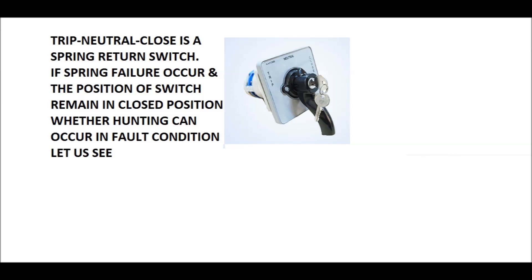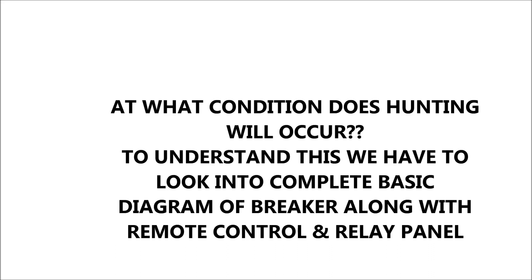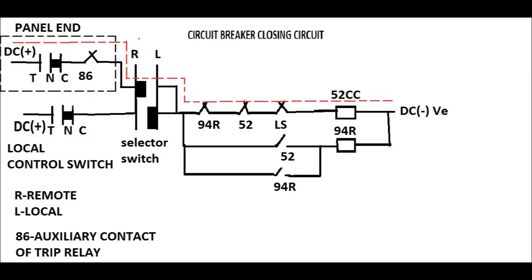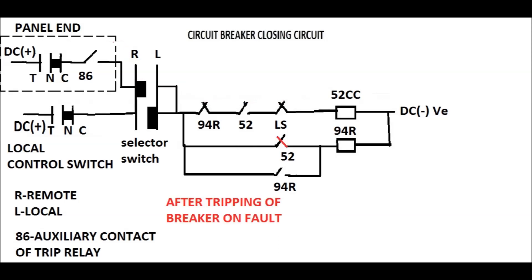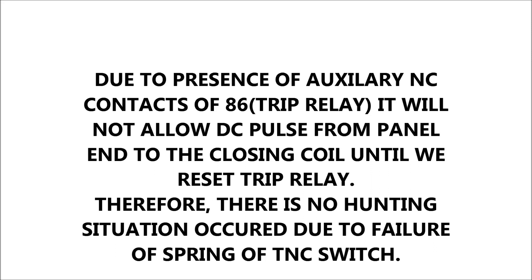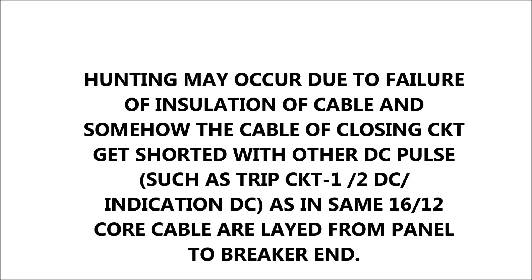At most sites, hunting may be thought to arise due to failure of the spring return of the TNC control switch. As shown in this figure, if we press the control switch to the closed position, it will automatically return to the normal position due to the spring. However, to understand whether spring failure can cause hunting in the absence of an anti-pumping relay, we must go through the complete circuit diagram from the panel end to the breaker end. In this complete diagram, you can see there is an auxiliary NC contact of the master trip relay, or 86 relay. If a fault occurs, the 86 relay will open and will not allow any DC pulse to the closing coil — so spring failure of the control switch has no relation to hunting.